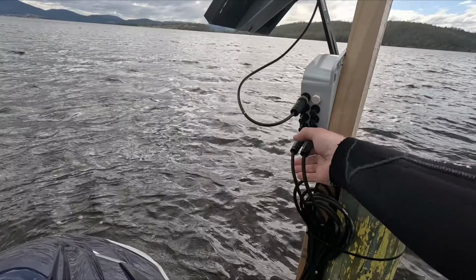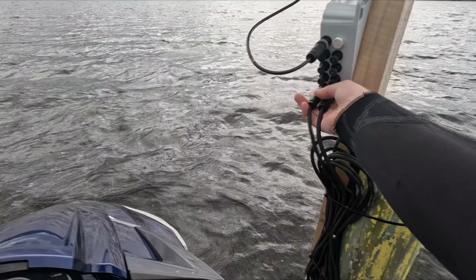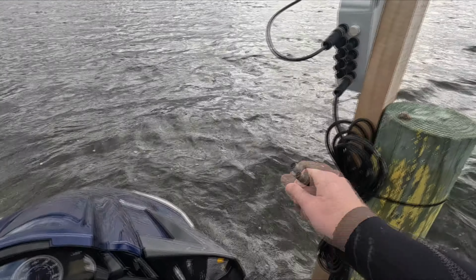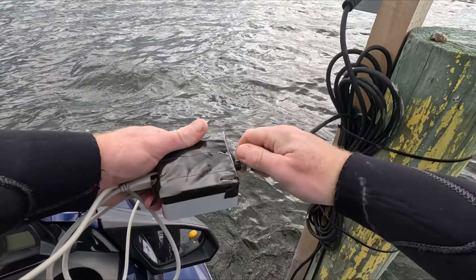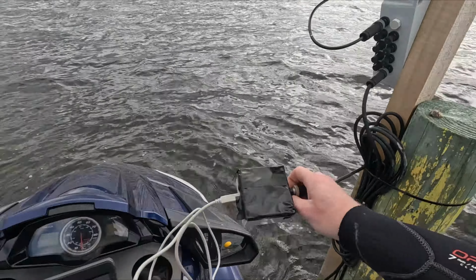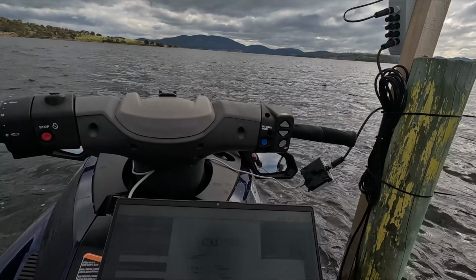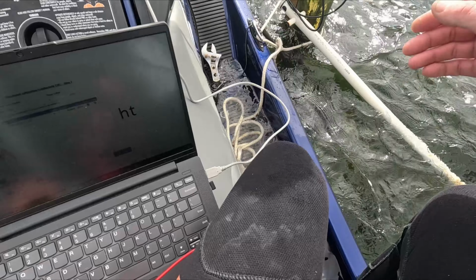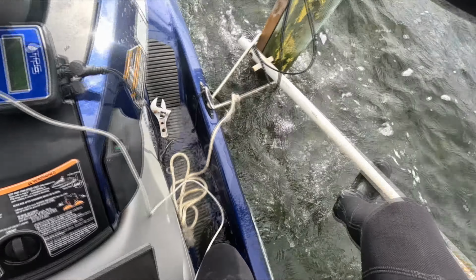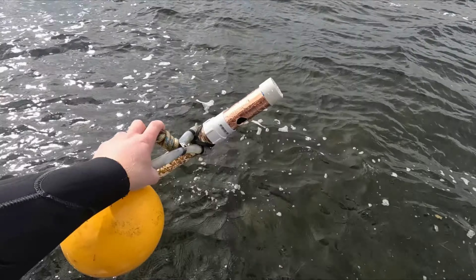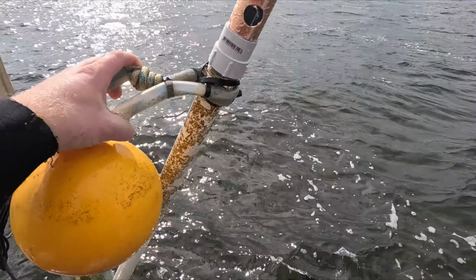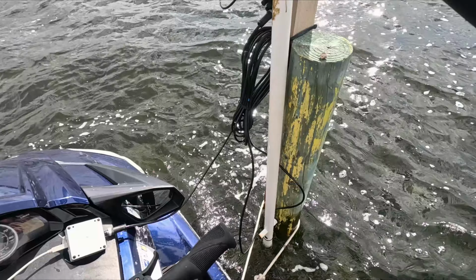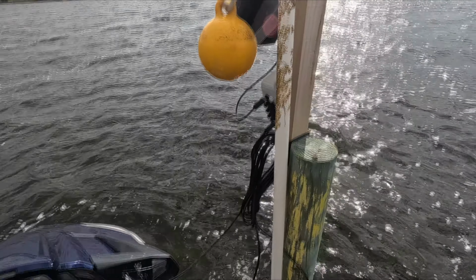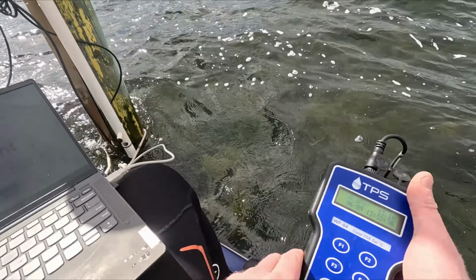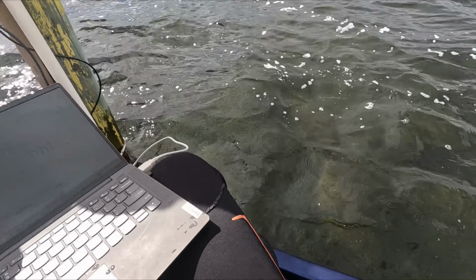Alright, so we're going to have to calibrate the sensor. So currently that process involves removing the sensor from the node, plugging it in to our little box here, which connects it to our computer. And what we've got to do is get a measurement first in no salty condition. So we'll pull the sensor out of the water. And we'll leave him in free air to dry. While we're waiting, we'll get our calibrated instrument and we'll deploy that into the water and let that settle as well.